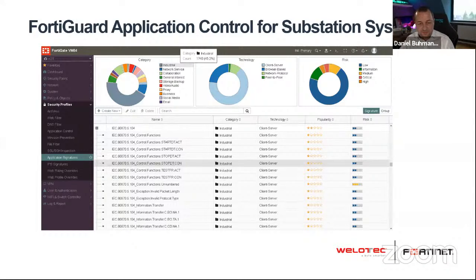But you can also dive deeper and look for the message that is sent, and go even one step deeper - you can put arguments like the ASDU address or the cause of transmission into this. We have customers in energy transmission getting these arguments from the control system and putting them as rules into their firewall, to make a control check if it's really what they are expecting. So they have their control system and firewall in a control center where all the messages are coming in from the field network, and they make a kind of plausibility control to check if it's the right message coming in.